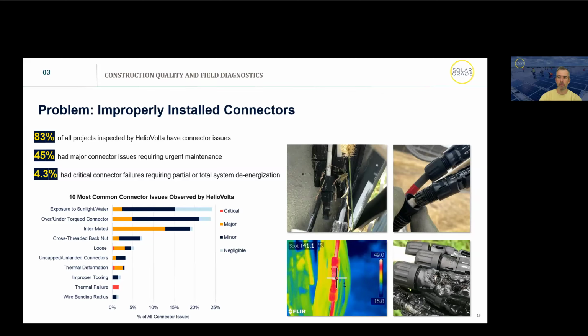The chart at the bottom shows the most common connector issues observed by Heliovolta: connectors exposed to sunlight, water, over torque, under torque, inter-mated, cross-threaded, loose, etc. On the right, we see photos of examples found in the field - uncapped connectors sitting on site for months during construction, or improperly made connectors. These evolve over time into overheating and failed connectors, as you can see on the bottom right.